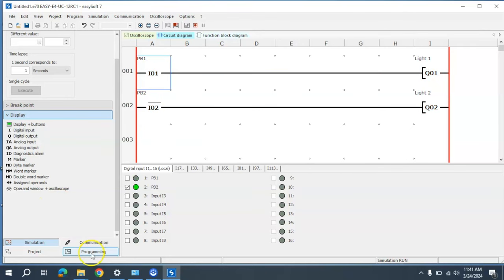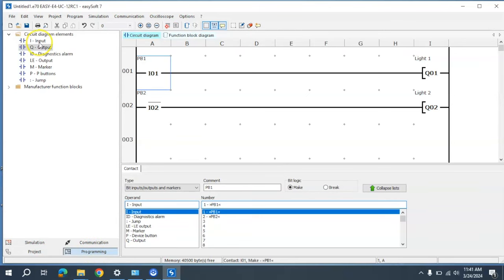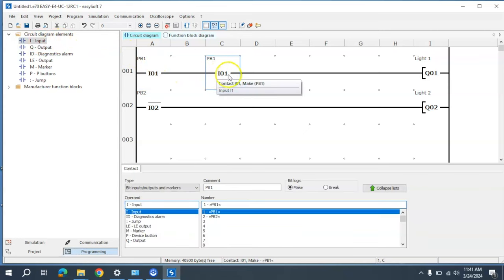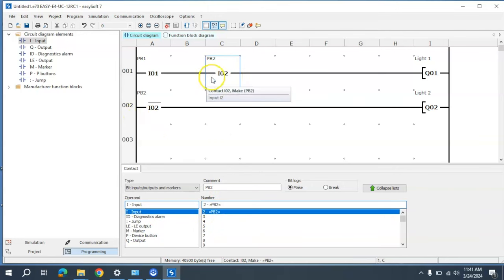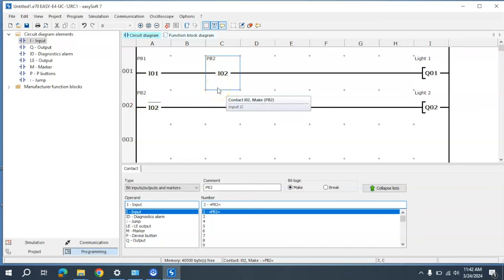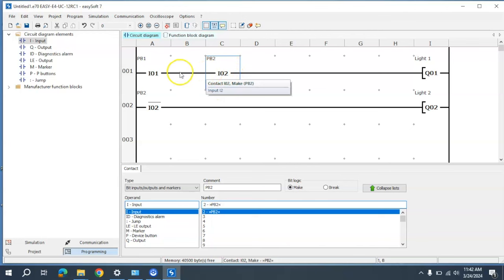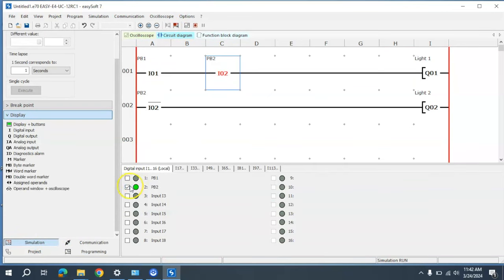Now if I come back to Program, I can modify this any way I need to. For example, I could drop another input here and make it input two. Notice these two inputs now have the same address, but one has a line over it making it a break, and the other is a make — so they will switch each other. Input two and input one are now in series. Going back to simulation and starting it, I can activate Push Button One and Push Button Two — Q1 comes on and Q2 comes off, because the rung went from a true statement to a false statement. When I deactivate either of them, it will go false.